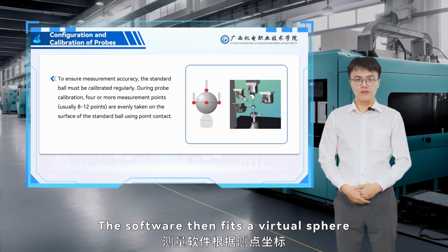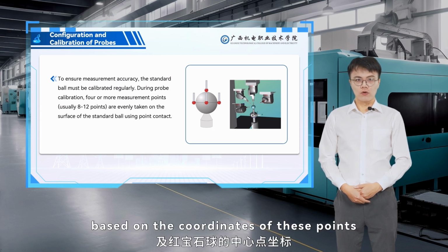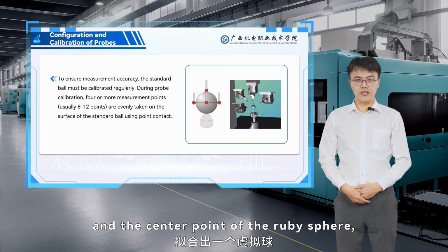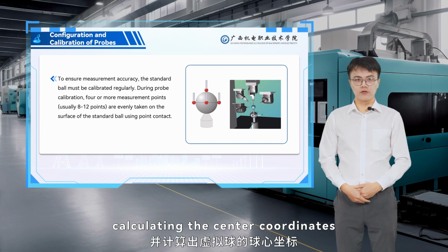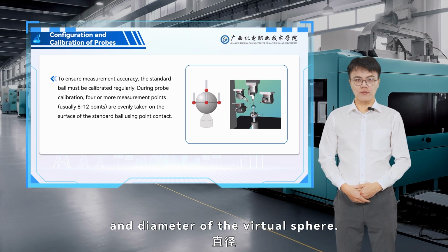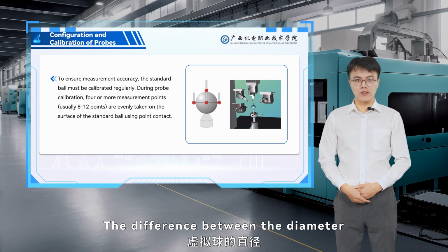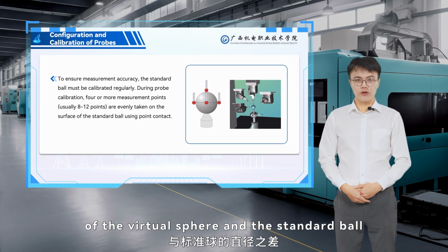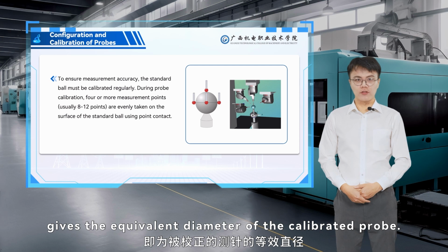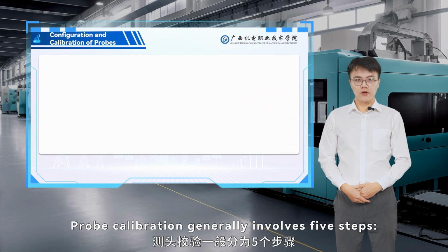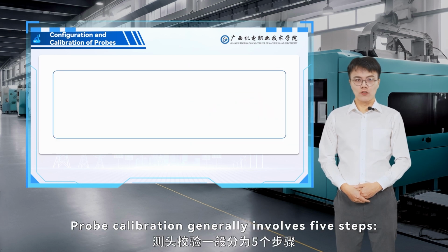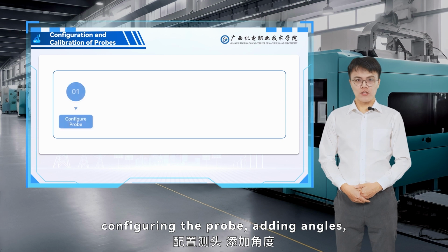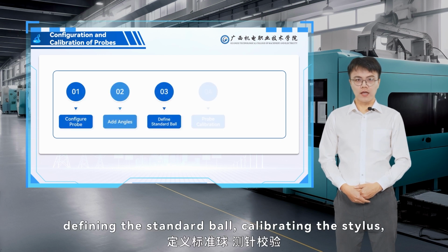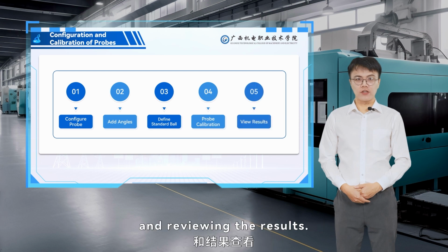The software then fits a virtual sphere based on the coordinates of these points and the center point of the ruby sphere, calculating the center coordinates and diameter of the virtual sphere. The difference between the diameter of the virtual sphere and the standard ball gives the equivalent diameter of the calibrated probe. Probe calibration generally involves 5 steps: configuring the probe, adding angles, defining the standard ball, calibrating the stylus, and reviewing the results.